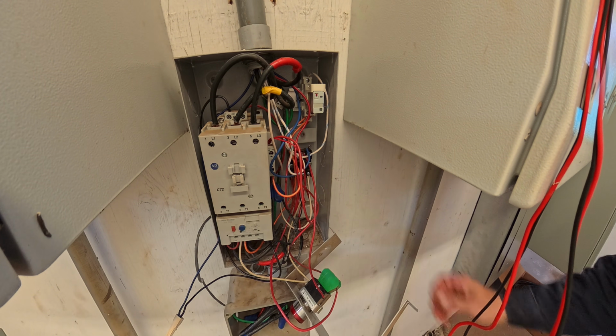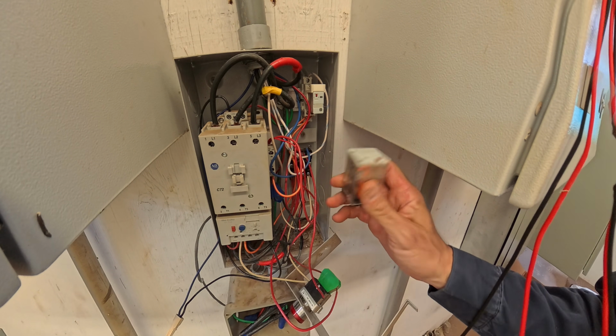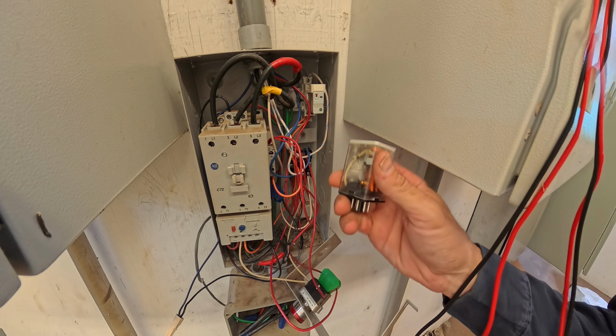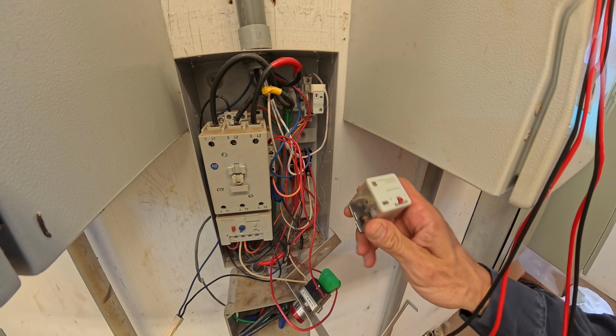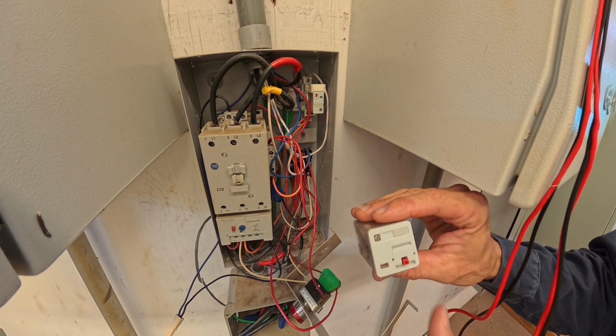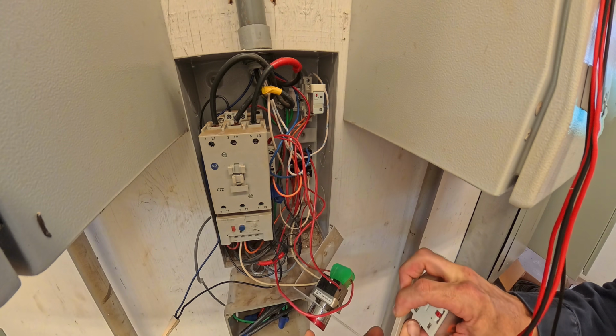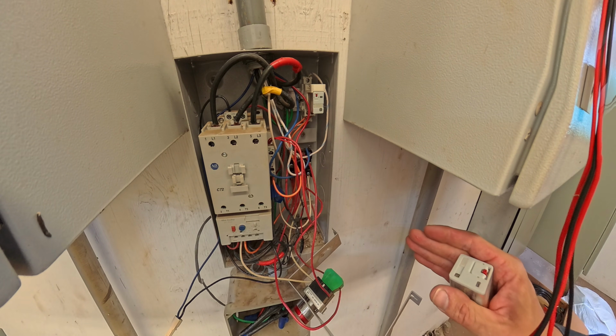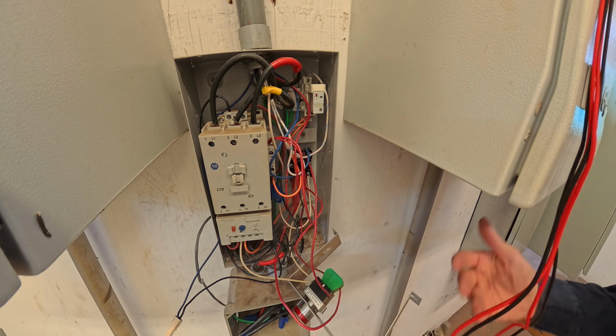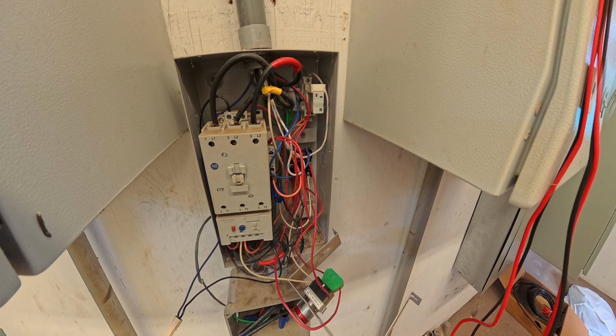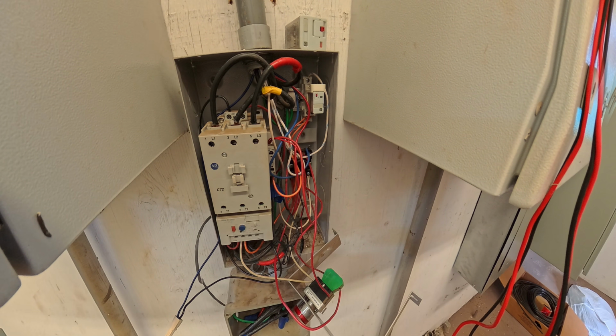So yeah, this is our run feedback interposing relay, and this is their low water reset relay. So when the float opens, it opens this relay until you close it momentarily by pushing this momentary push button. Then that holds it closed until the float opens again. So I don't really need any of that logic anymore. This is all temporary until they get their permanent pump installed with a new VFD starter and all this gets demolished, and this is why it's so disheveled. So for today, simplicity is going to be the key.